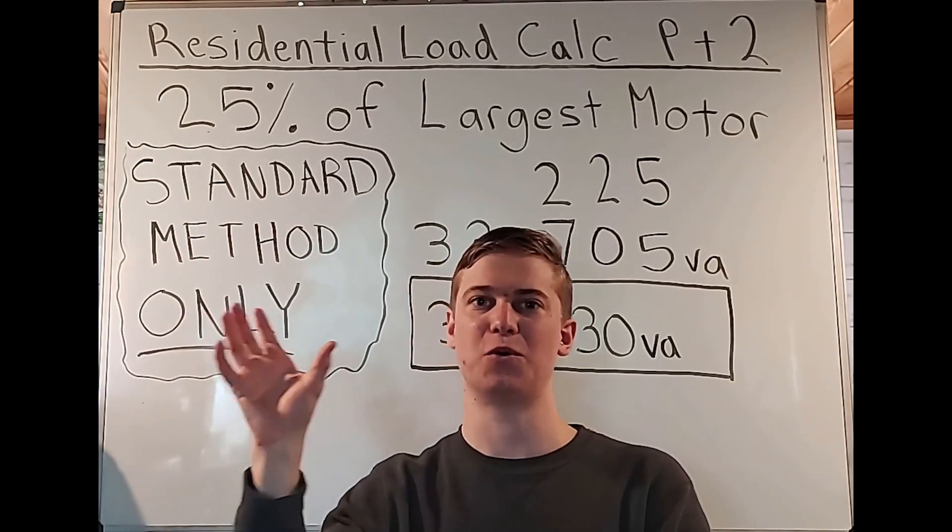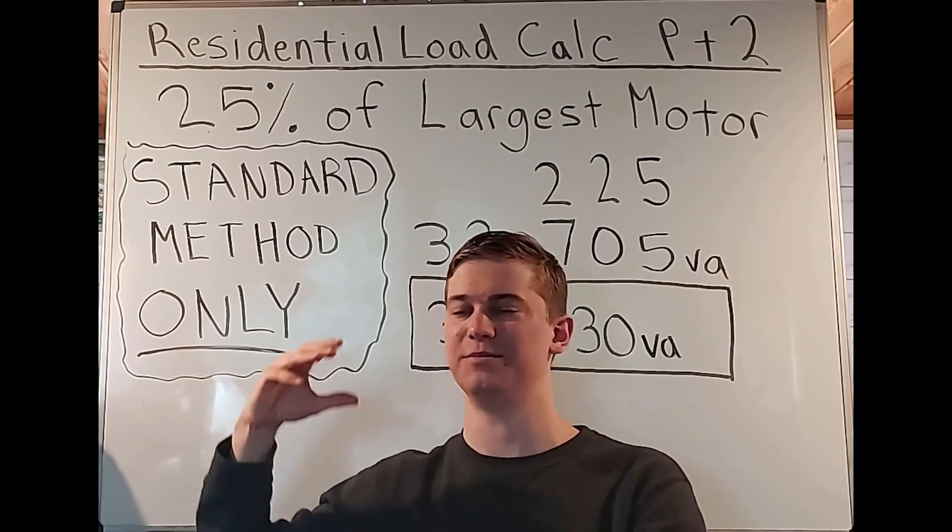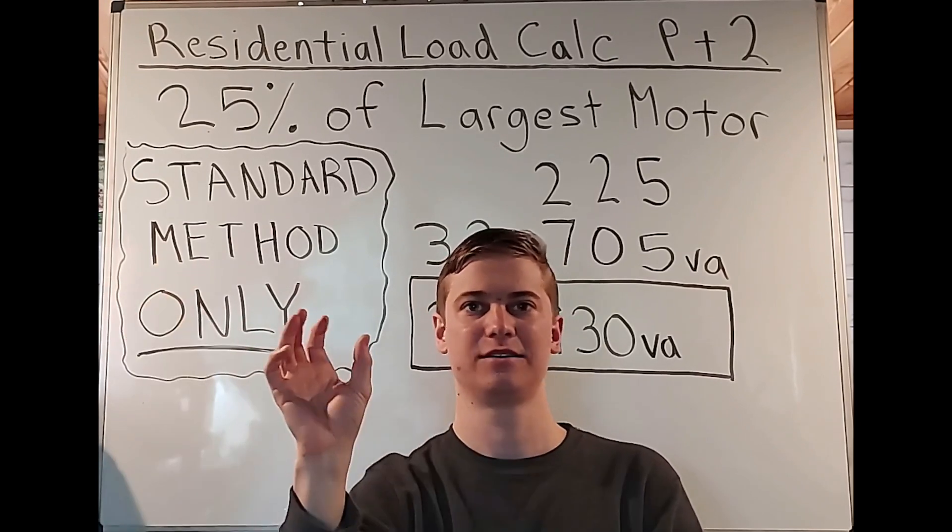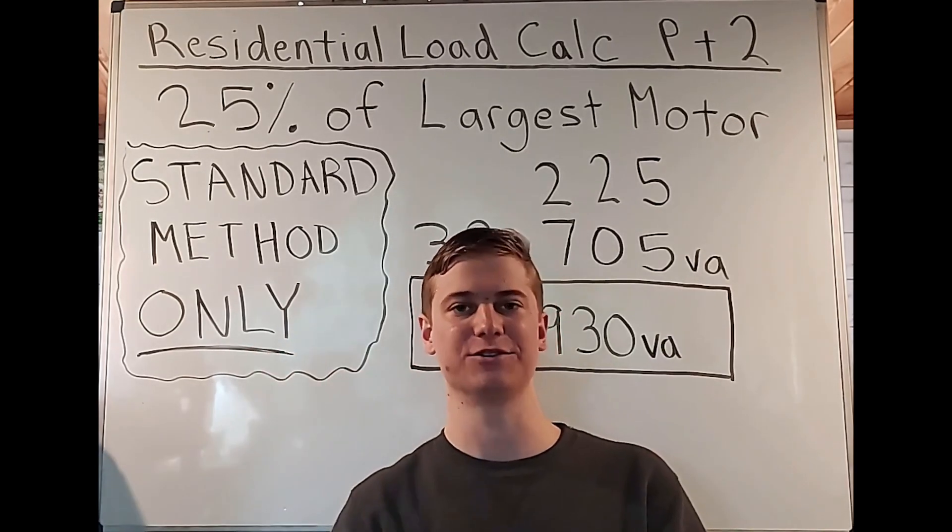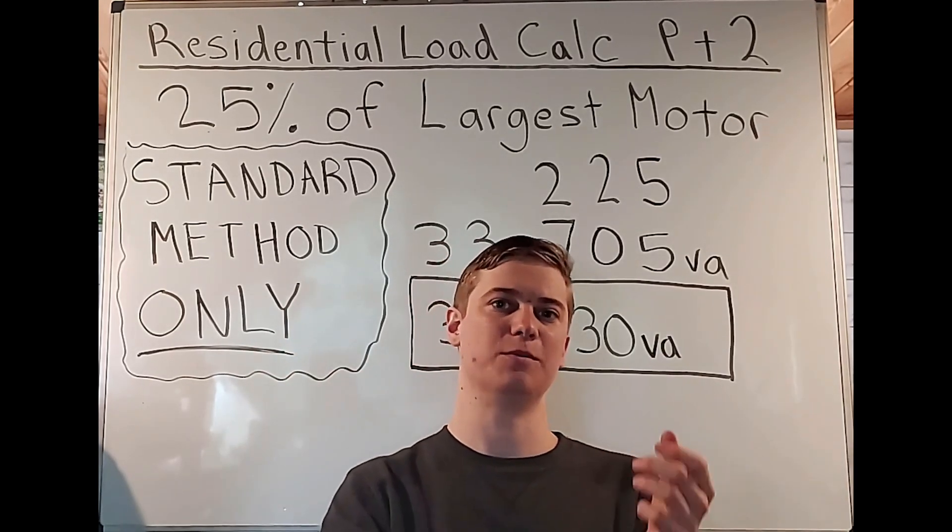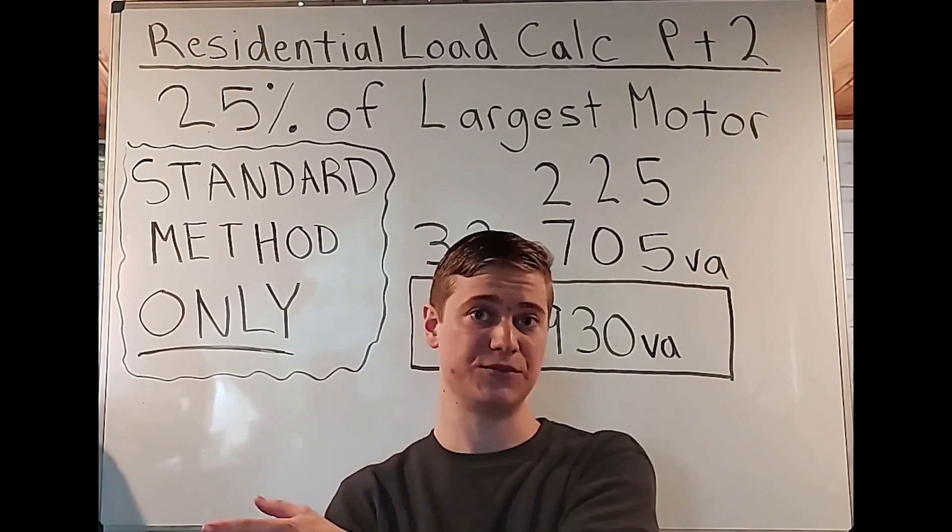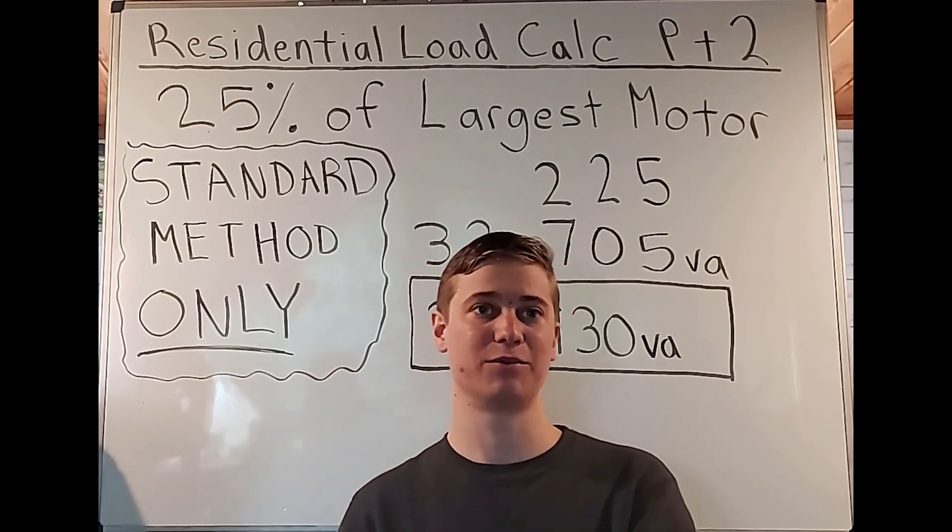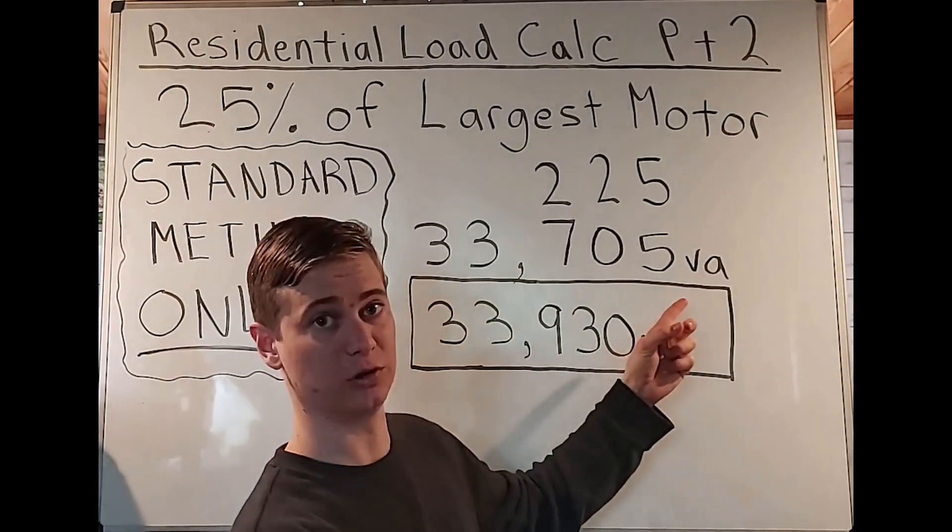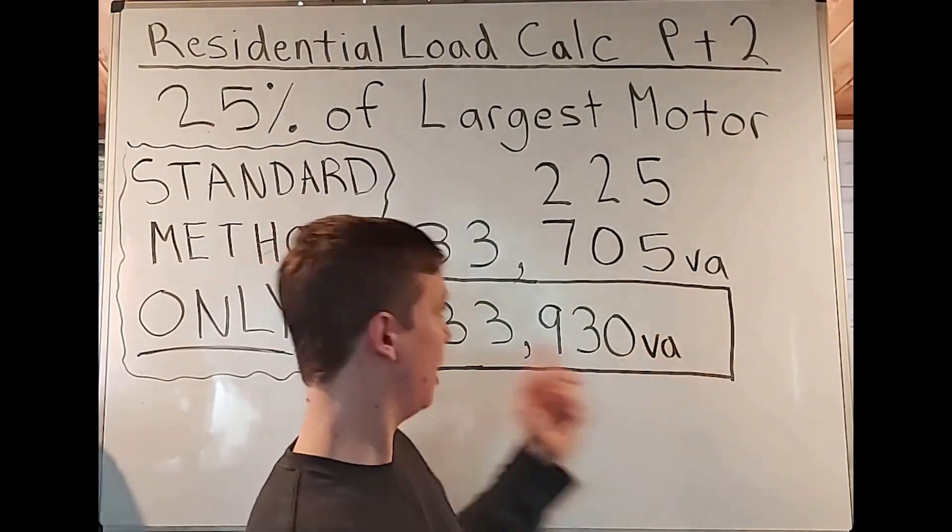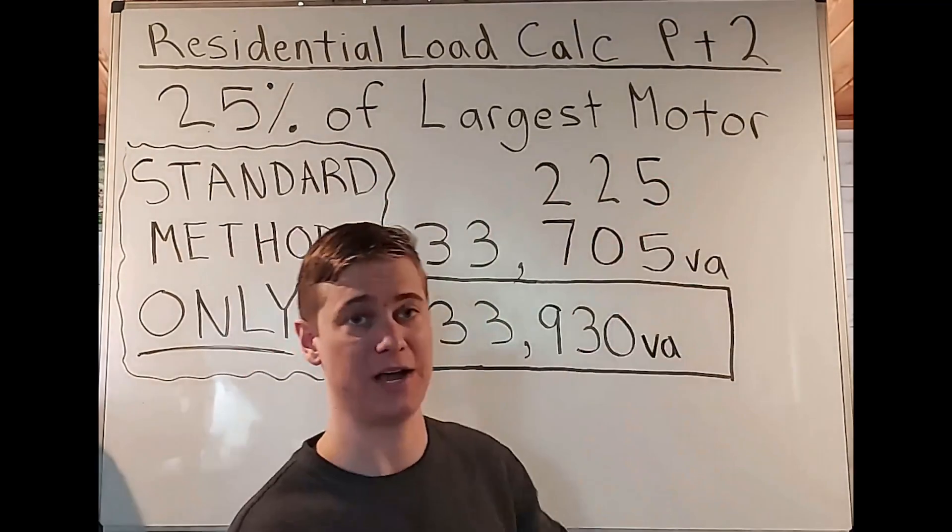Not just the one that has the largest volt amps and contains a motor, but the one with the largest motor. We're going to take that at its full load. Whether we did the demand factors with the four or more or not, we're going to take it at face value without any demand factors. And then we're going to multiply that by 0.25.